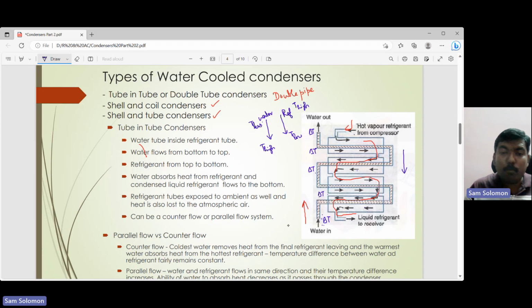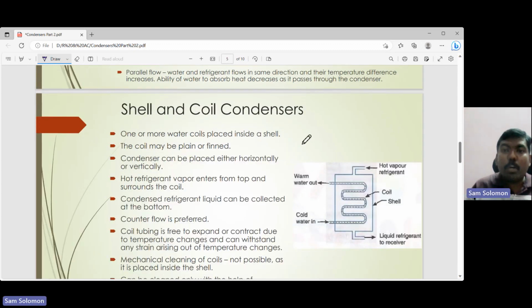The temperature difference between water and the refrigerant fairly remains constant, whereas in the parallel flow, the ability of the water to absorb heat decreases as it passes through the condenser. So that is your tube in tube condenser. The next one is the shell and coil condenser. So you have an outer shell. What is shown here, this rectangle, is your shell. The shell has an entry and an exit. From the entry, you have the hot vapor refrigerant, and through the exit, you have the liquid refrigerant.